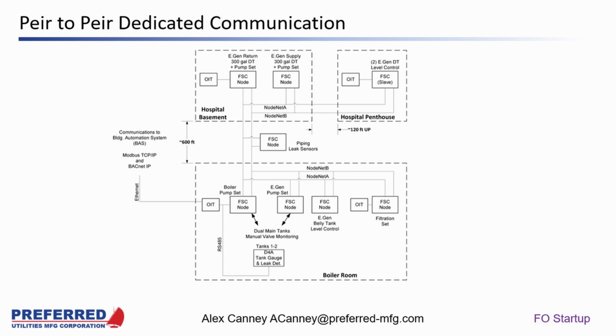With old style pump sets using a standard PLC, every wire that came from the day tank went right back to that control panel, with wires running through the building up, down, and around. Now with NodeNet communications, all the field devices on each day tank go to that specific node, and you just have 2 little wires going back to the control panel so it knows when to supply oil to it. So you cut down on the amount of AWG or stranded wiring tremendously.